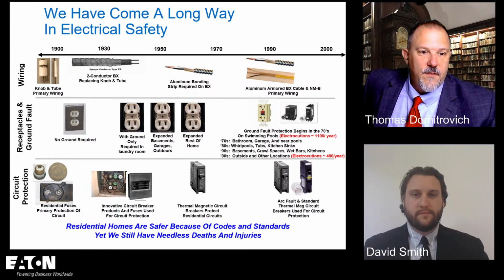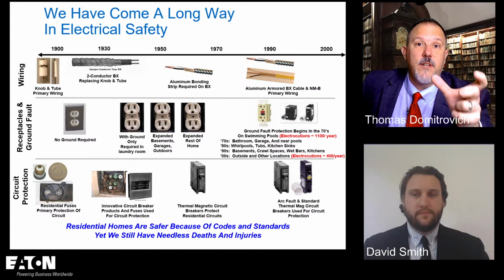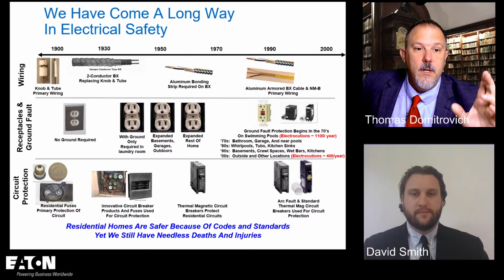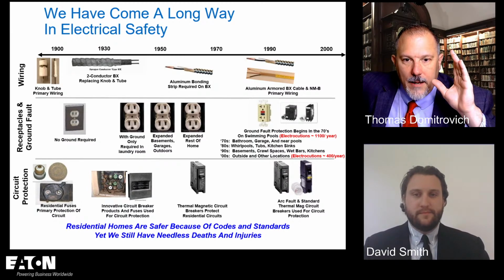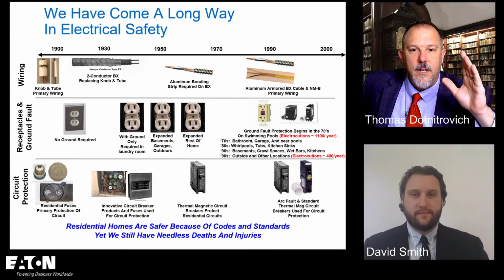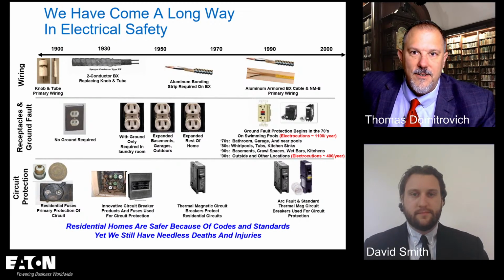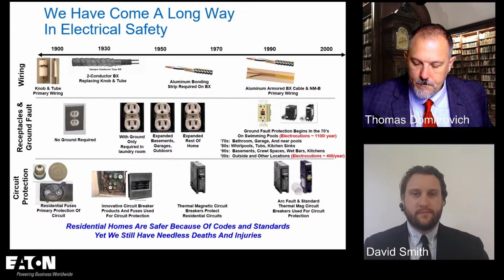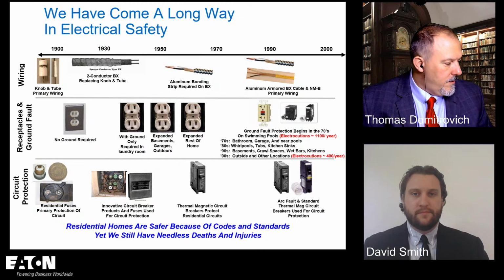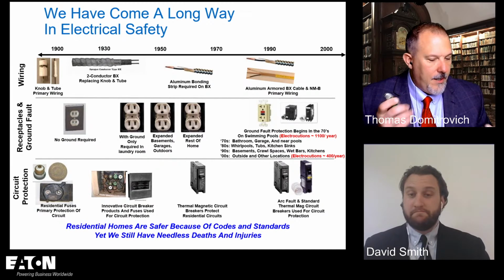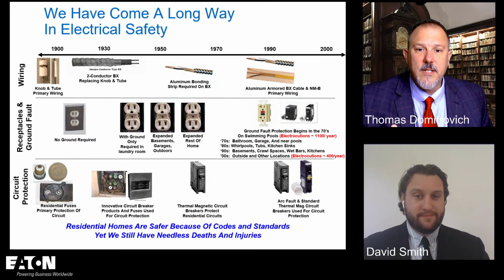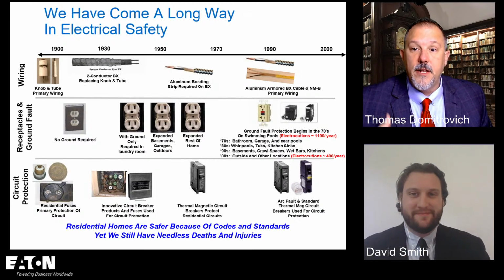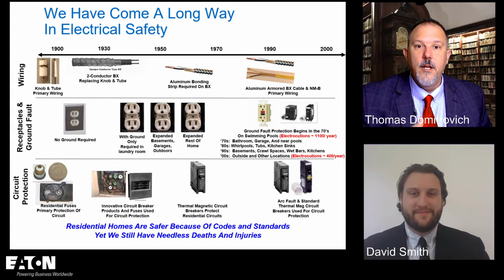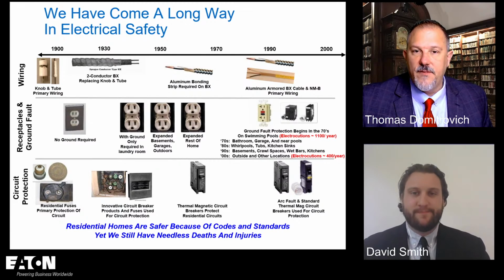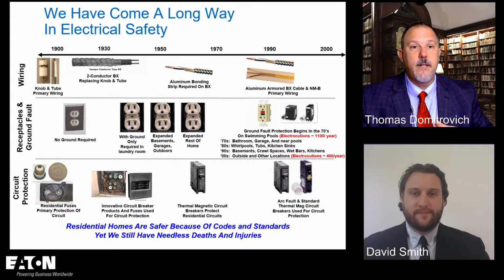And circuit protection went from those round fuses, and in some cases the fuses didn't even have an enclosure around them, right? Up to a breaker that can actually communicate. Okay, I talked about this with, who was that with? Anyway, we talked about the whole fact that we have circuit breakers now that communicate, and you can get data remotely from them, and AFCIs have a microprocessor in them, and they detect bad arcs.